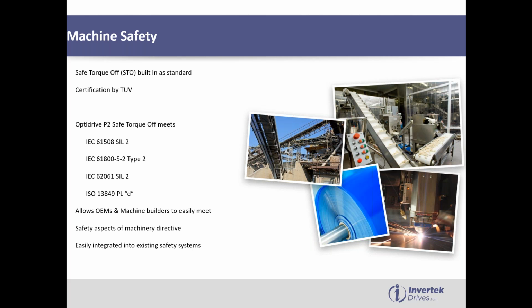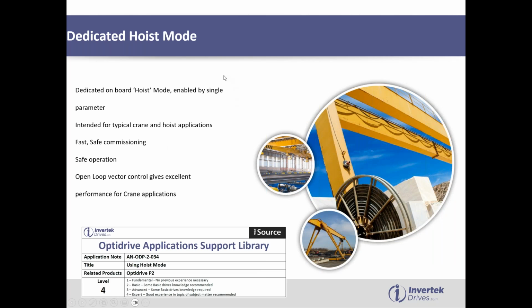So anywhere in the plant that needs light gates, things like that. If you open the gate or if you cross the barrier, then the drive will automatically stop. So that's built in as standard on the P2. We have a dedicated hoist mode. Hoist mode is just selected by a single parameter, which makes it very nice and easy to safely commission a crane or a hoist application very quickly.